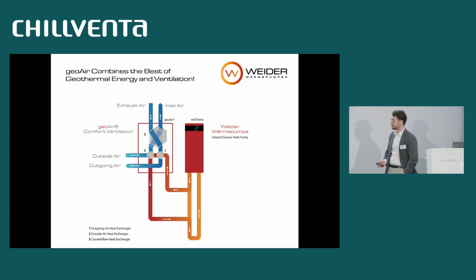And in summer, some people may argue that it's also a problem when the outside air is too hot, right? Then the inlet air also becomes too hot. In summer, the brine actually cools down the outside air, which is part of a passive cooling. You can imagine it like that. And it's also more comfortable inlet air temperatures.